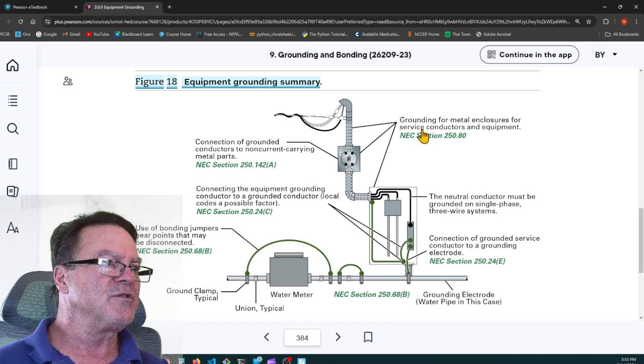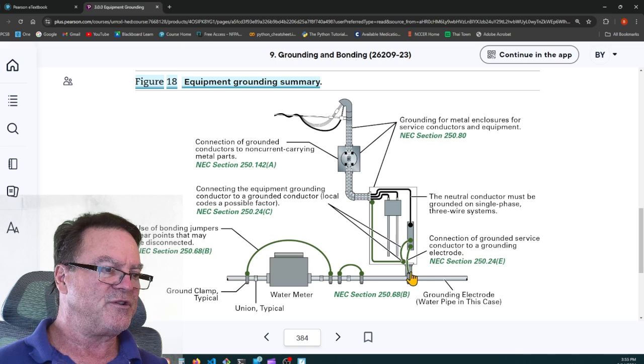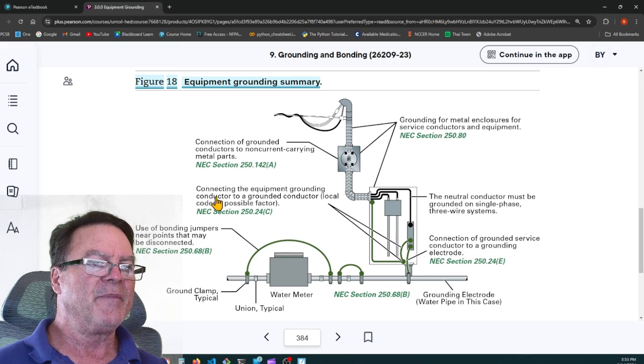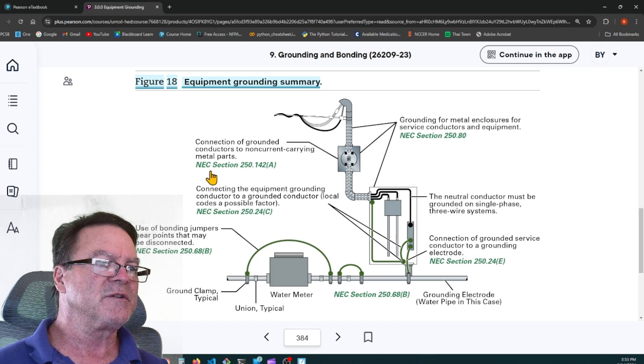It says grounding for metal enclosures for service conductors and equipment. It's Article 250.80. The neutral conductor must be grounded on single-phase 3-wire systems. Connection of grounded service conductor to a grounding electrode, NEC section 250.24E. Connection of grounded conductors for non-current carrying metal parts, NEC section 250.142A. Connecting the equipment grounding conductor to a grounded conductor.